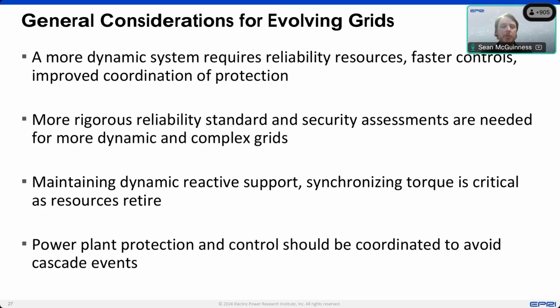We've already mentioned dynamic reactive power support and synchronizing torque as both being very critical, especially as you get changes in resource mixes. And finally, I will always say this as a protection engineer: power plant protection and control should be coordinated to avoid these cascade tripping events.